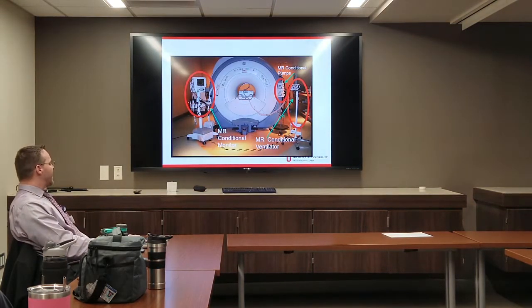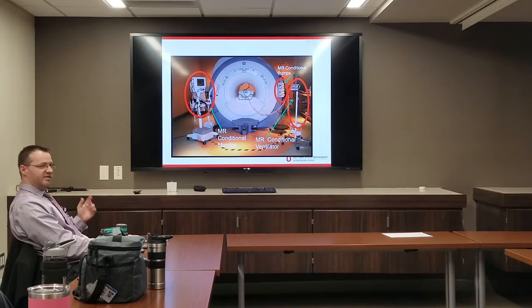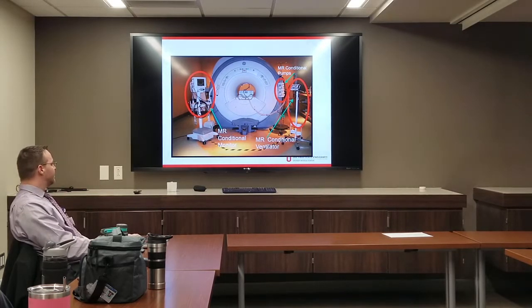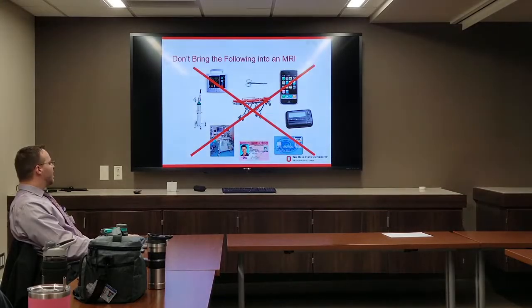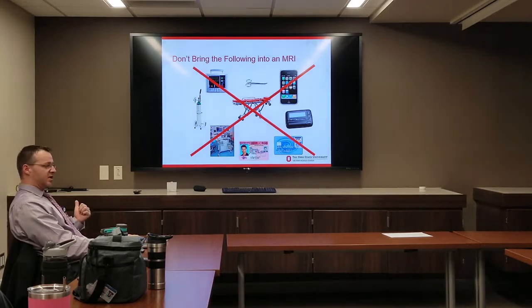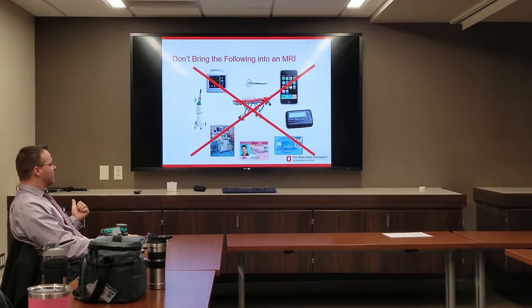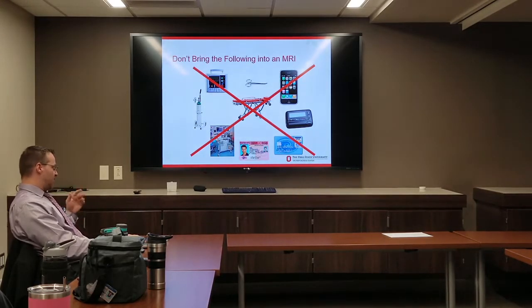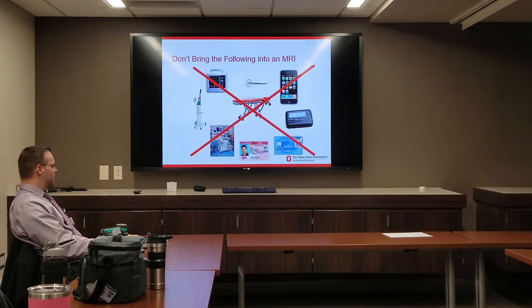Examples of MR conditional equipment include conditional monitors, conditional pumps, or a conditional ventilator. Things you don't want to bring in include non-MR conditional monitors, phones, hemostats, carts, O2 tanks, credit cards, paper — anything like that.